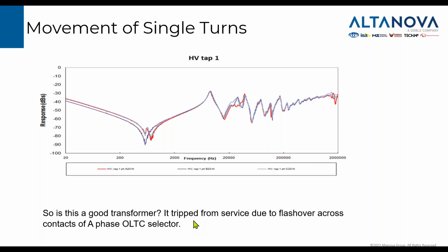So the transformer was basically disconnected, oil was drained, the tap changer selector compartments were open, and initially there was an open circuit on phase A, and then there were some sparking marks on the selector. Everything was repaired and reinstated, so the transformer could be tested in a condition without oil.